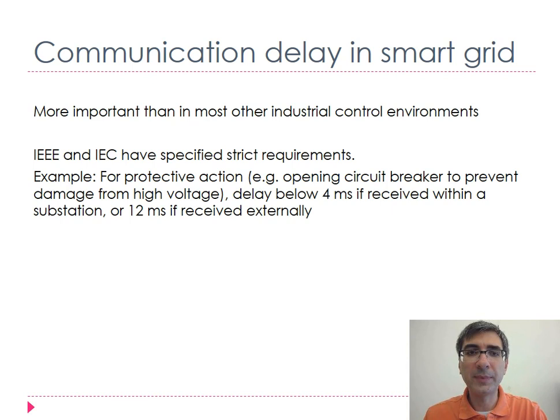An attacker wouldn't affect confidentiality much in relation to communication delay, and perhaps not integrity, but would go for availability. If one delays communication using some form of denial of service attack, having connected to the network, or perhaps a jamming attack if wireless communication is involved, the delay will go significantly over the 4 or 12 millisecond limits, and this will start affecting the integrity of the protective action.